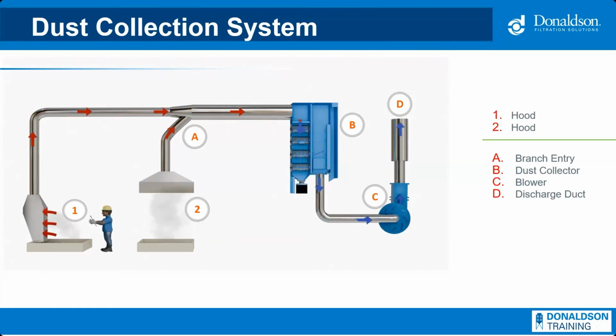And making all this happen is electrical controls, essentially the brains behind the system, communicating with all the main components, including things like the fan, the collector, the cleaning when that occurs, and any sensors that may alert the user if there's an issue, etc. If one component of the dust collection system is poorly designed, the whole system is affected.